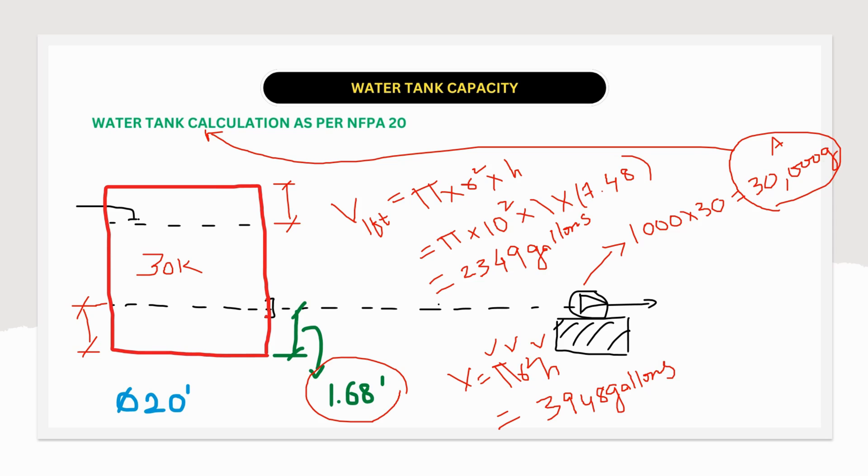Now we need to add 30,000 gallons plus 2,349 gallons plus 3,948 gallons. Then only we are going to get the actual water tank size required based on NFPA 20 requirements. So the total needed capacity would be A, B and C. So when we add this, the total capacity would be 36,297 gallons.